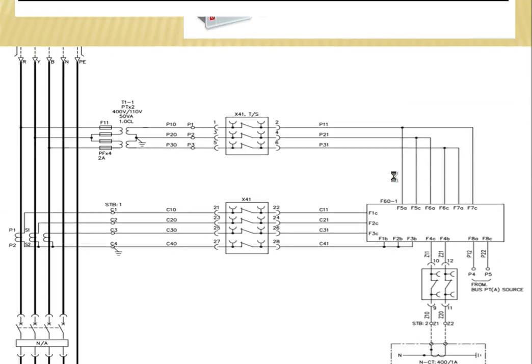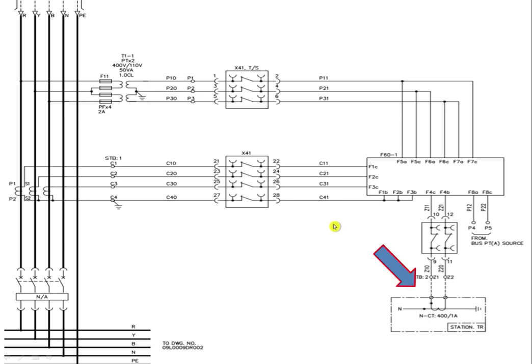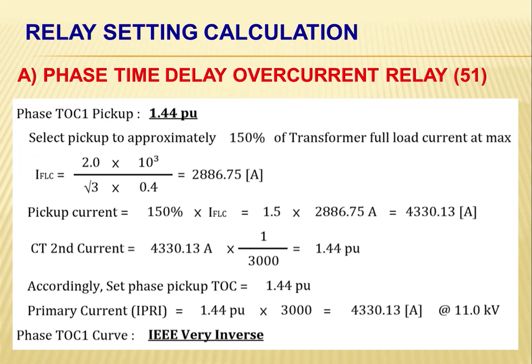Okay, so the location of our zero sequence current transformer is connected to the grounded neutral of our station transformer, because this CT will be connected also to our ANSI relay 50G, the instantaneous overcurrent relay, a ground fault overcurrent relay. Okay, so now let's start on our relay setting calculation.